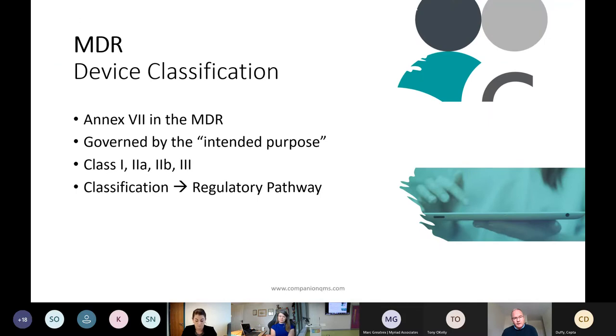One of the things that's changed under the MDR is device classification. There have been several changes. I'm not going to go into the weeds on what's changed in each rule, but it's all clearly written in English, in Annex 7 of the MDR. Once you've decided the intended purpose of your medical device, you'll be able to apply those rules to determine the classification for your device.